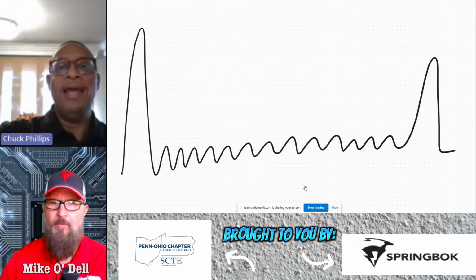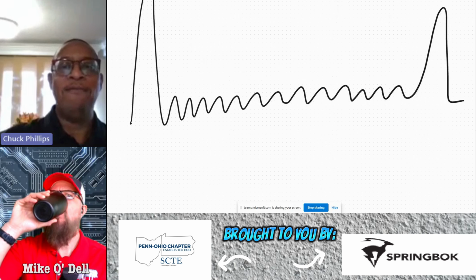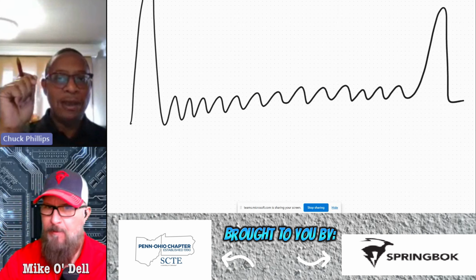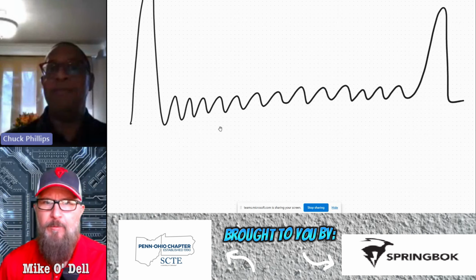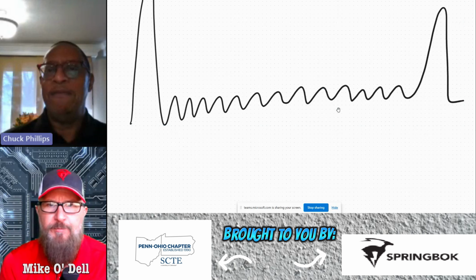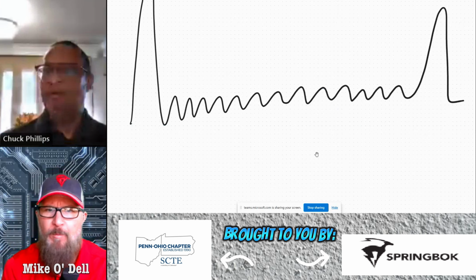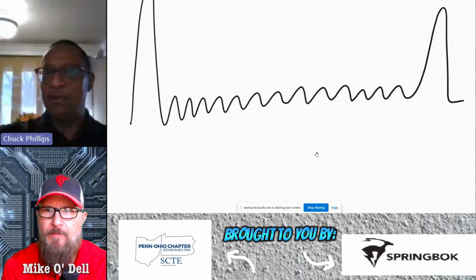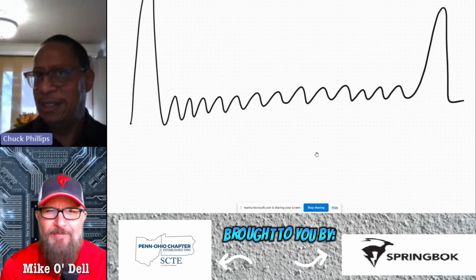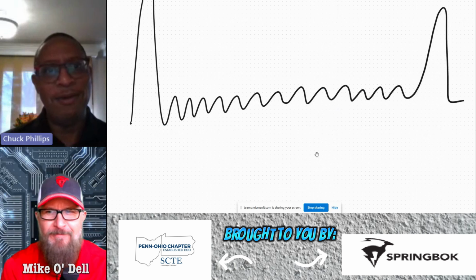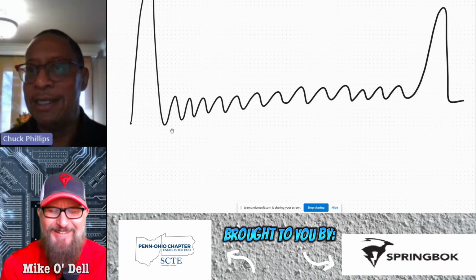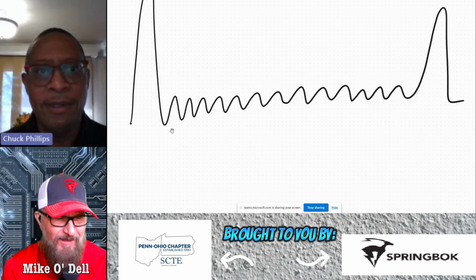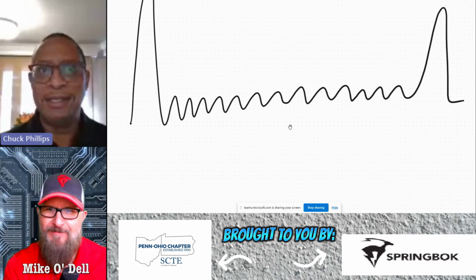Not uncommon, people will show me a waveform like this, and since they're all stuck on what it's supposed to look like, people will say, so when I get a waveform like this, I've heard that a squiggly line like that means there's water in the cable. Is that what that is? And I'm going to be a smart aleck. I was born that way. I'm going to take a look at it and say, 1,200 feet of water? I don't think so.